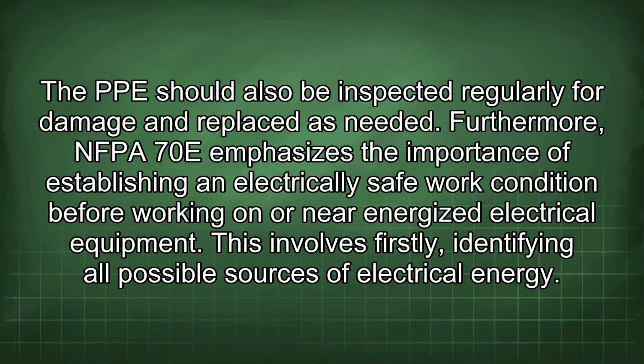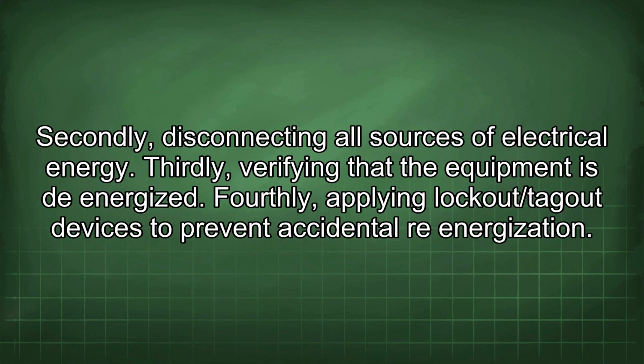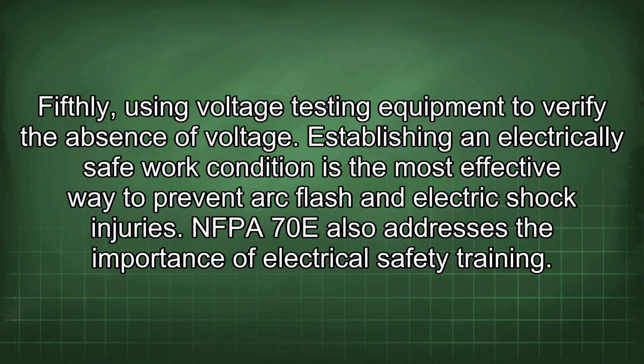Furthermore, NFPA 70E emphasizes the importance of establishing an electrically safe work condition before working on or near energized electrical equipment. This involves, firstly, identifying all possible sources of electrical energy. Secondly, disconnecting all sources of electrical energy. Thirdly, verifying that the equipment is de-energized. Fourthly, applying lockout/tagout devices to prevent accidental re-energization. Fifthly, using voltage testing equipment to verify the absence of voltage. Establishing an electrically safe work condition is the most effective way to prevent arc flash and electric shock injuries.